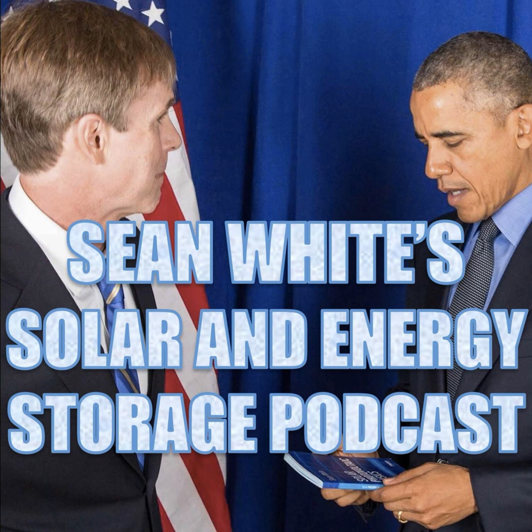They almost got rid of Article 480, and there's people that still want to do it. But they say it's the telecom people that are keeping this here, so they don't have to follow as strict of rules. You're typically talking about lead acid batteries, or maybe some nickel-based batteries. We got NiCads in there. So some of these Article 480 definitions only apply when you're doing 480. Cell, container, electrolyte. Electrolyte is the ion transport mechanism medium.